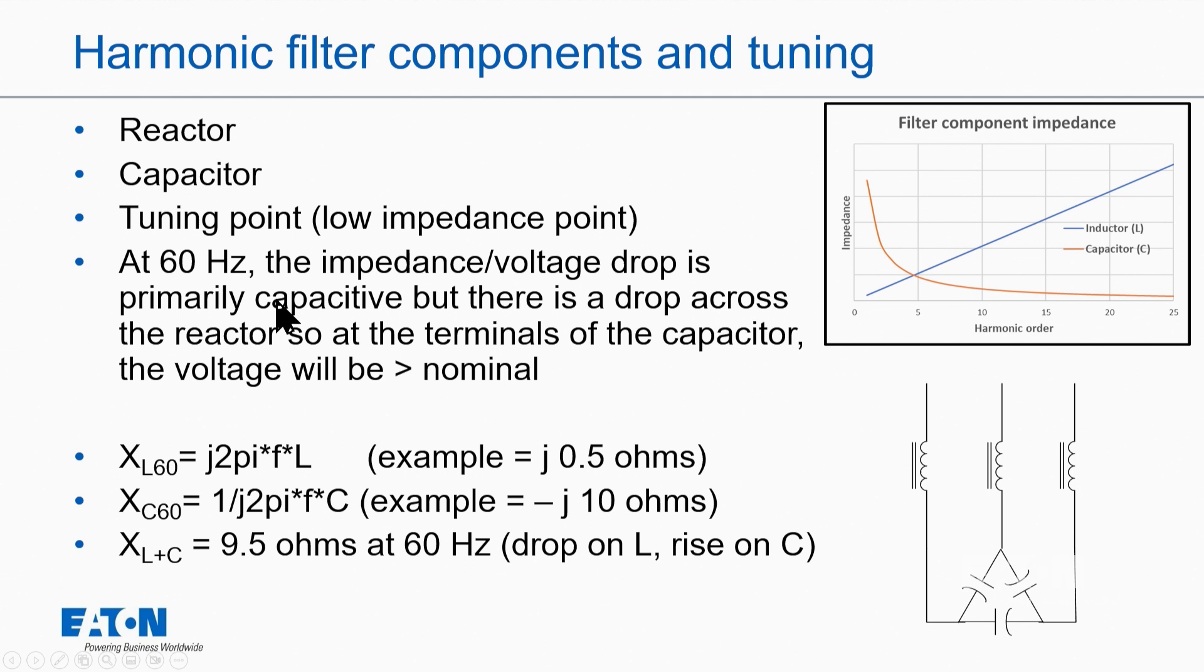At 60 hertz, the impedance or the voltage drop is primarily capacitive, but there's also a drop across the line reactor. So at the terminals of the capacitor, the voltage will be greater than nominal.